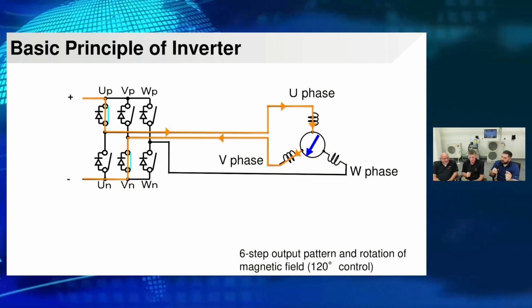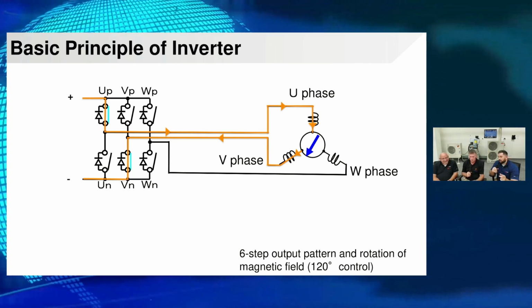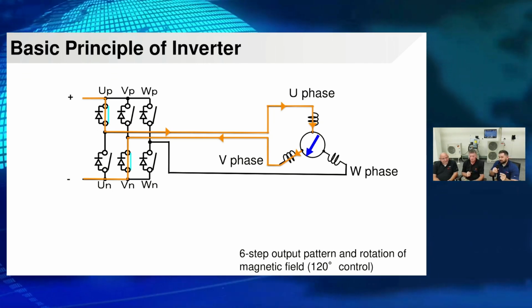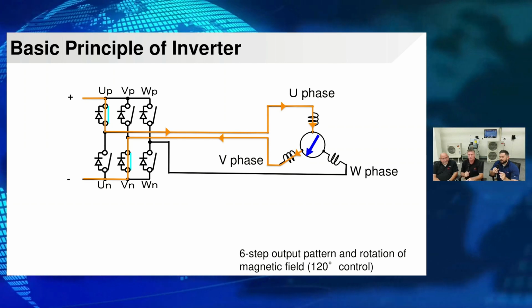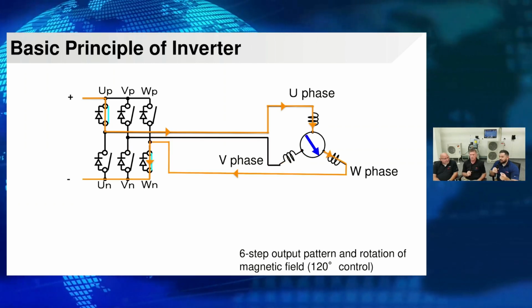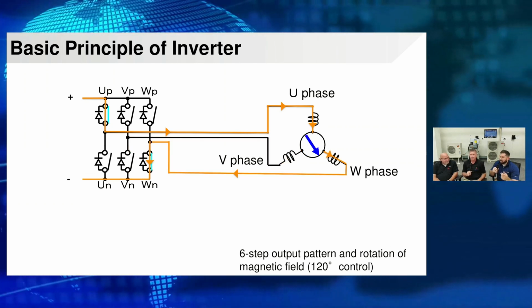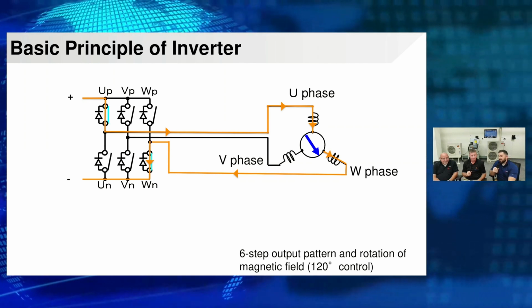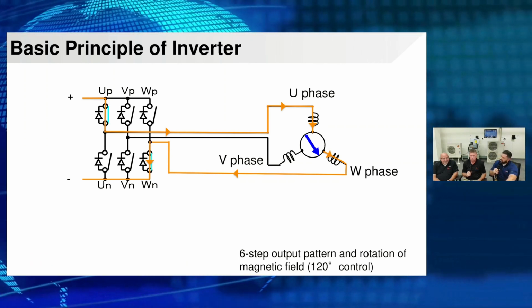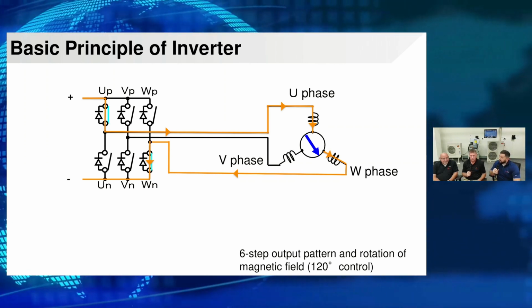So every time those IGBTs switch - as you scroll through, you'll see it switches different switches in order to make that rotation. Now we're going to energize the W, and that's going to give us our path back on W. Every time we do that, we're just getting that rotational force on that compressor. That is how the compressor is driven.